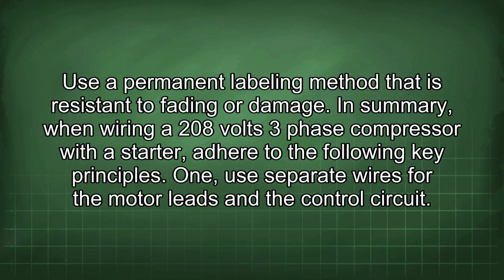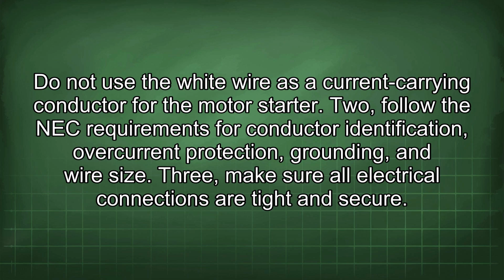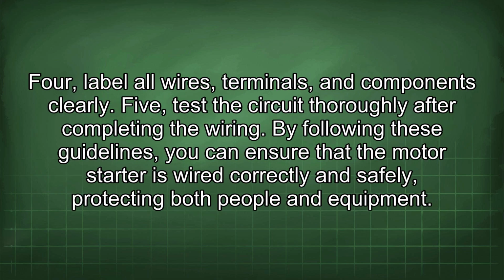In summary, when wiring a 208 volts 3-phase compressor with a starter, adhere to the following key principles. 1. Use separate wires for the motor leads and the control circuit. Do not use the white wire as a current carrying conductor for the motor starter. 2. Follow the NEC requirements for conductor identification, overcurrent protection, grounding, and wire size. 3. Make sure all electrical connections are tight and secure. 4. Label all wires, terminals, and components clearly. 5. Test the circuit thoroughly after completing the wiring.